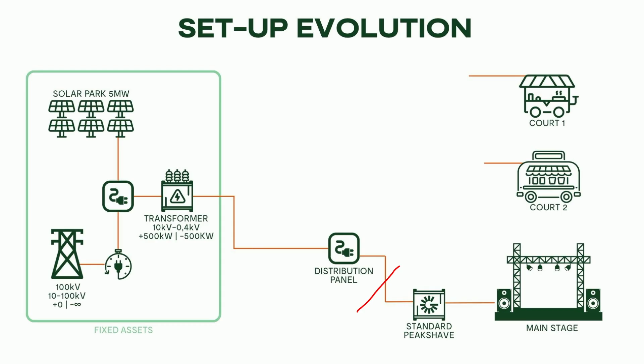So in that instance, that battery that's sitting there is going to grid follow. Yes. So when it's in peak shave mode. But if the grid were to fail here, it would revert immediately to grid forming mode, and that happens very, very quickly. 4 milliseconds. So the stage wouldn't have noticed any change in power output. Not at all. This change from following to forming happens every single time you do a cycle. On a generator or something else.